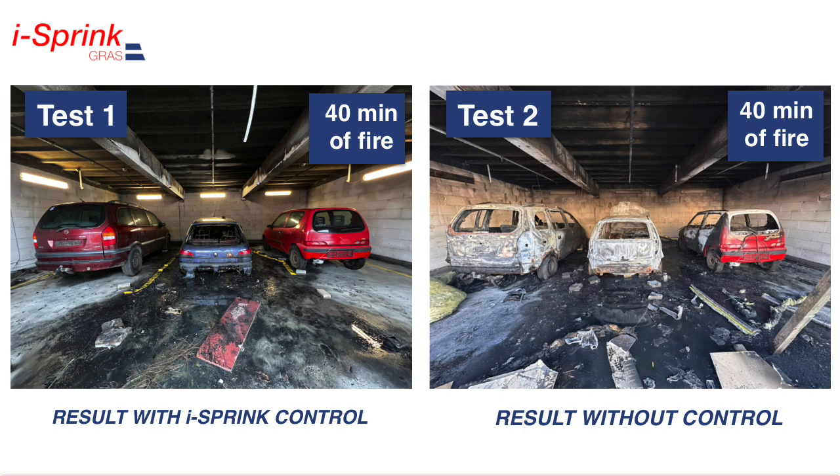The conducted tests of the i-Sprink system confirm the effectiveness of early detection, proper localization and indication of the fire location, as well as effective control against the spread of fire to other vehicles and building elements. Continuous water spraying made it possible to significantly reduce the temperature and obtain favorable conditions for rescue operations for fire brigades. The i-Sprink system is one of the most effective automatic fire control systems for electric vehicles, designed for both existing and newly designed facilities.